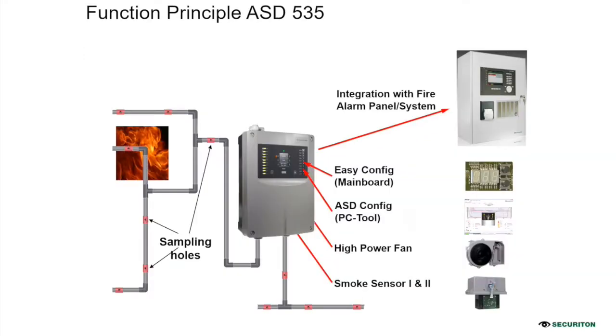Our ASDs can be integrated with the fire alarm panel also, to control the system remotely, and connected on the same loop of the fire alarm system, which takes care of the other applications as well. So if you have a building with point detectors and other systems as well, and you have an HVDC valve hall in that area, you can connect our aspirating smoke detector in that same fire alarm panel, in the same loop itself. We can use a one channel or two channel aspirating smoke detector depending on the size and area of the valve hall.